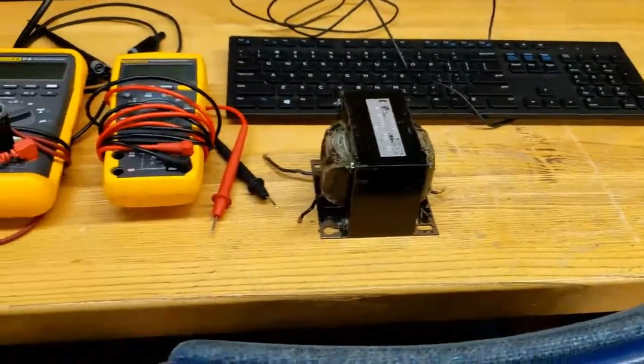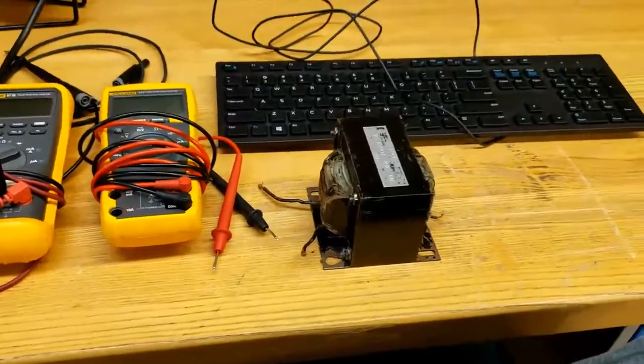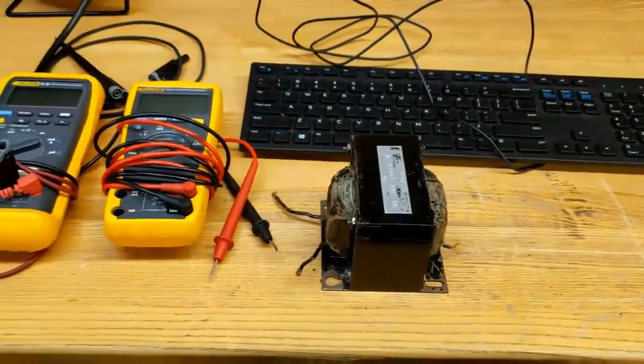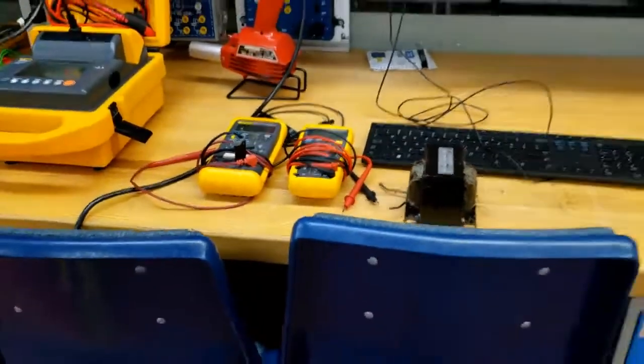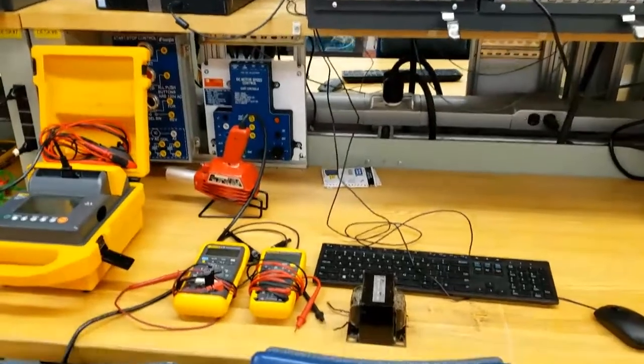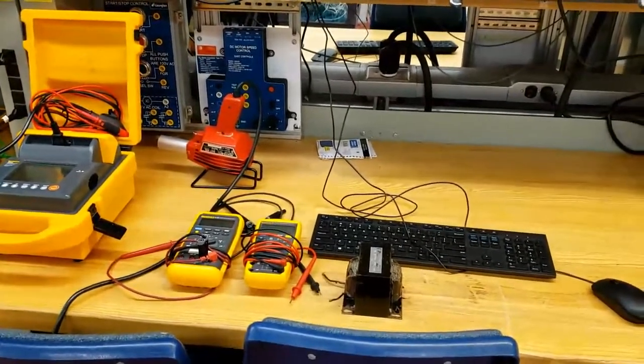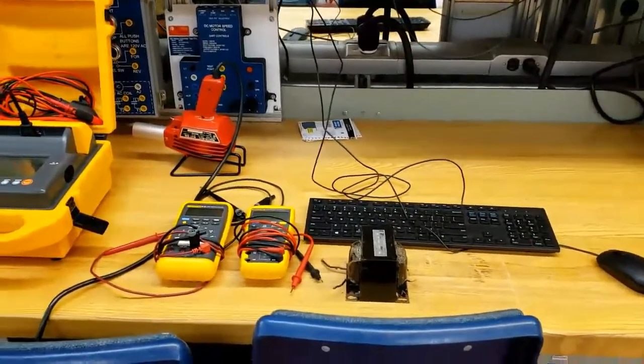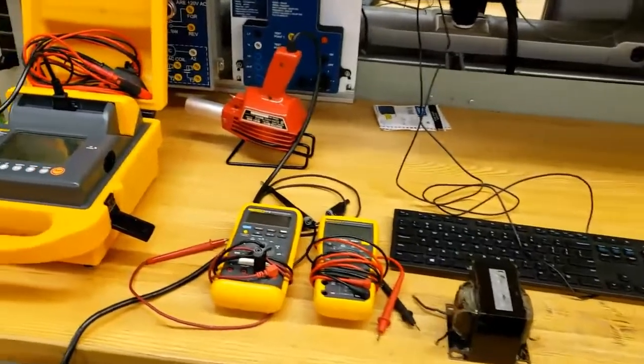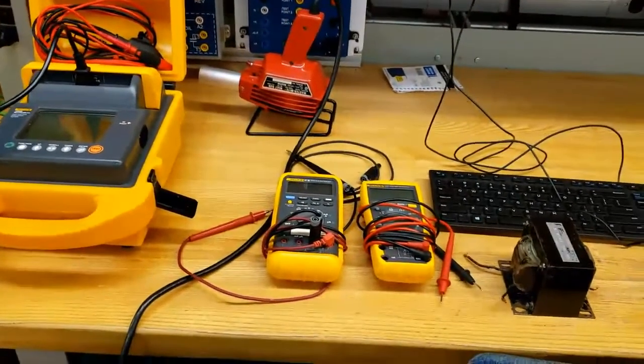At the end of 10 minutes, you start stepping the voltage up. You go to 40 volts for 60 seconds. You then go to 50 volts for 60 seconds, 60 volts. So 1 minute each until you get to 100 volts, then you stop. Re-megger and see what the readings are like.